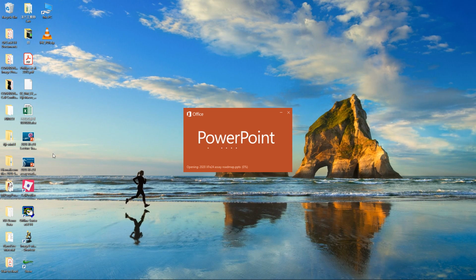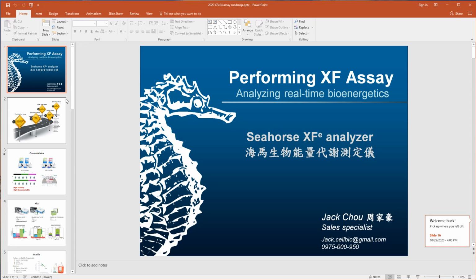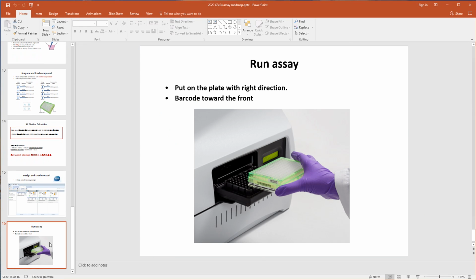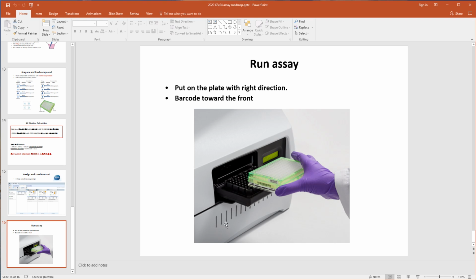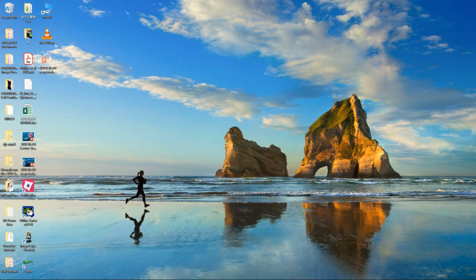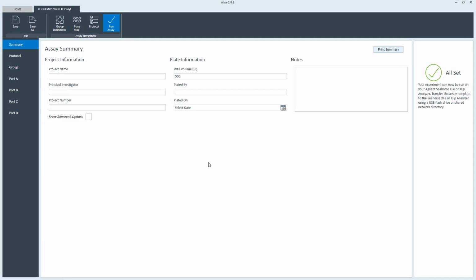Once you check the save location, finally the instrument will make the tray come out. Then you put the sensor cartridge onto the tray and click the button again. It will go in and take around 20 minutes to do the calibration.